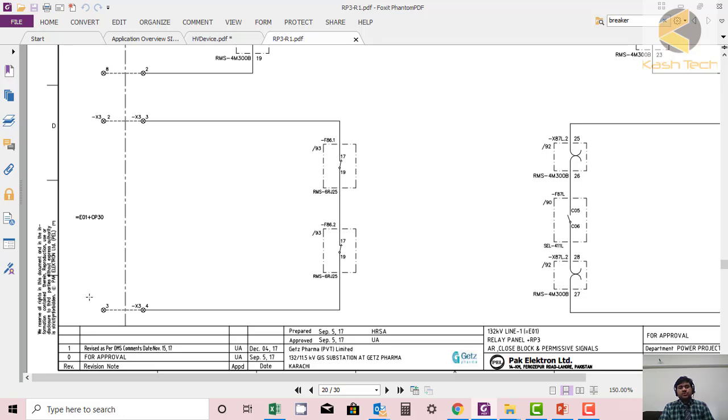Also the indication will be available on the control panel if any of the lockout is operated, so operator can check easily. You should call a protection engineer to come and verify. After verification they can reset the lockout and breaker can be closed. So this is the lockout circuit in our drawing. Thank you.